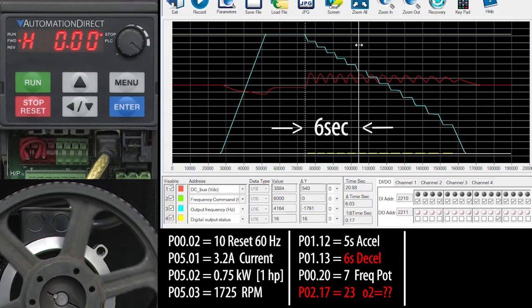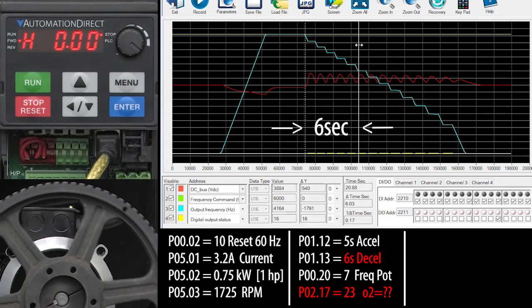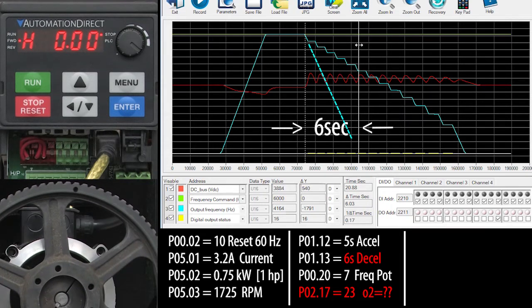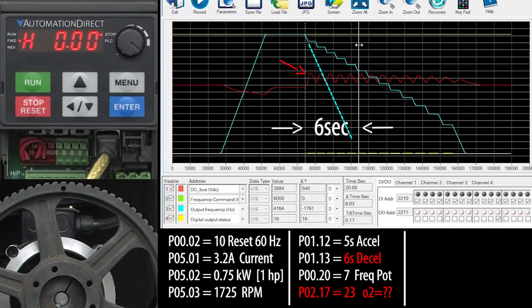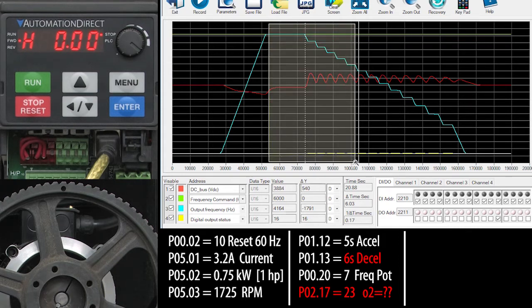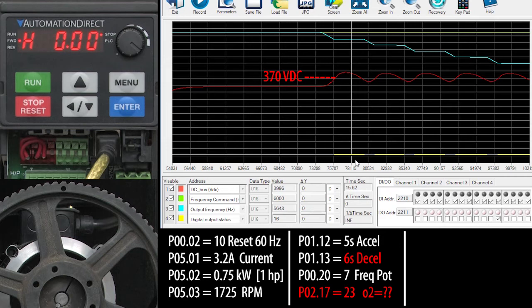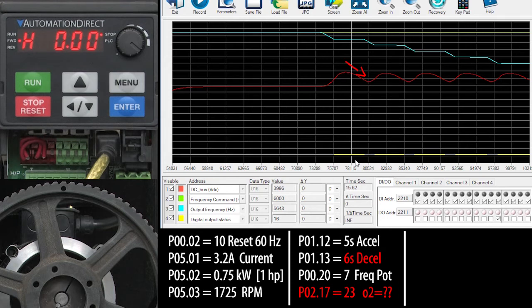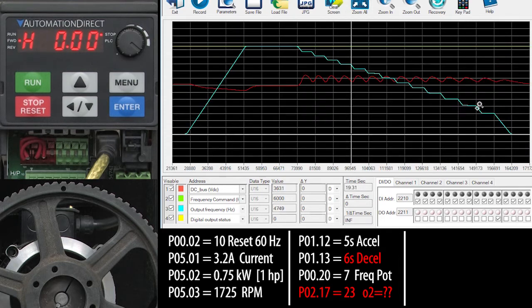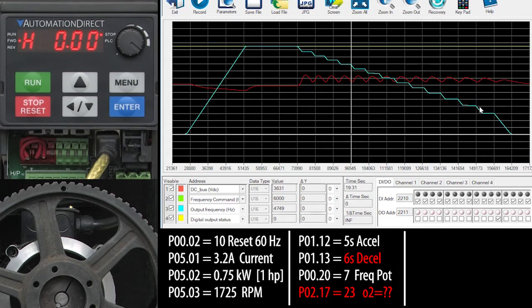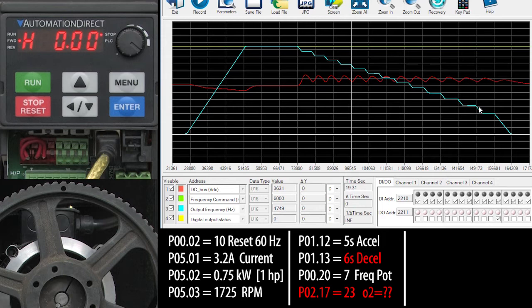We asked it to ramp down over 6 seconds and it started to do that. But when it saw the DC bus get too high, let's zoom in on that, looks like around 370 volts, the drive automatically held off on the deceleration until the DC bus got back down to a more tolerable level. And then it re-engaged deceleration until the DC bus got too high again and just kept repeating that over and over and over again until things settled out.